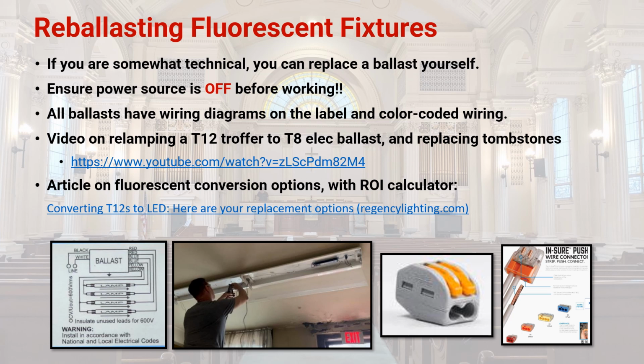So if you are going to reballast your existing fixtures, you can technically replace a ballast yourself. It's considered a maintenance item in the electrical regulations in most jurisdictions, but again, check to be sure. If you're going to replace it yourself, of course, make sure the power is off at the switch and the circuit breaker, and make sure it's taped, labeled, tagged, or you post a watch to make sure no one turns the power on while you're working in that fixture. All these ballasts on the labels have a wiring diagram, and it shows you which wires go where. And in North America, we have standardized color-coded wiring: blue, red, and yellow.